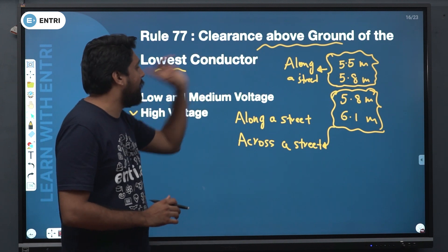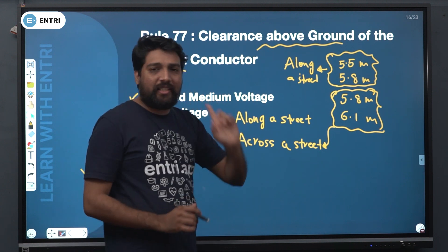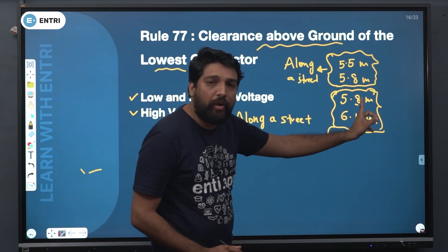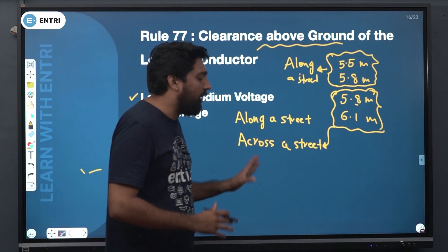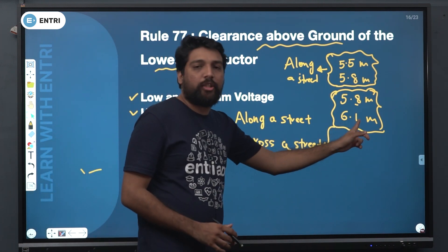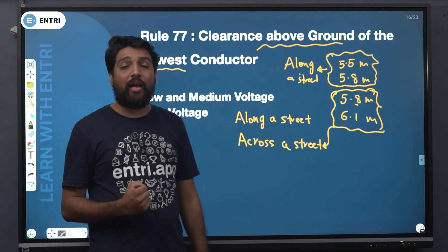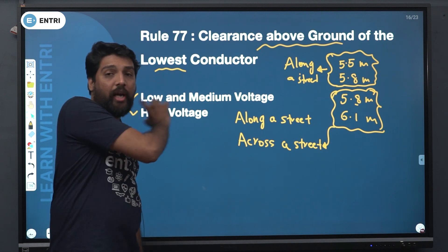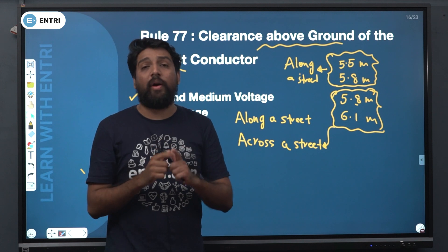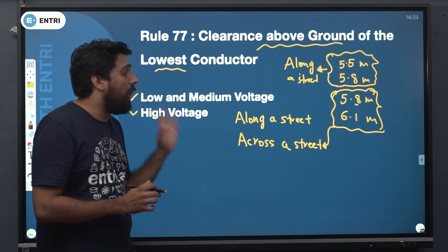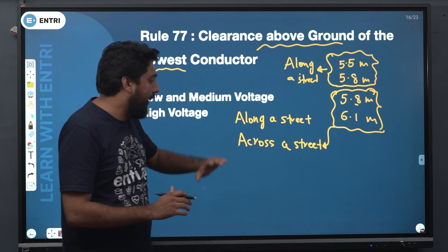For clearance above ground of the lowest conductor in a low and medium voltage line across a street, the value is 5.8 meters. For clearance above ground of the lowest conductor in a high voltage line across a street, the value is 6.1 meters. So the four values: along a street — 5.5 for low and medium voltage, 5.8 for high voltage; across a street — 5.8 and 6.1.